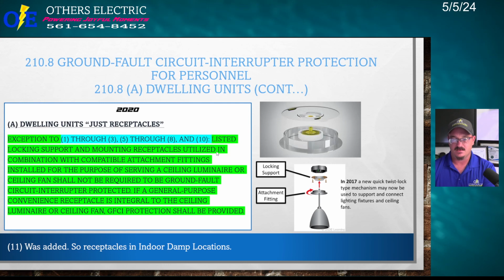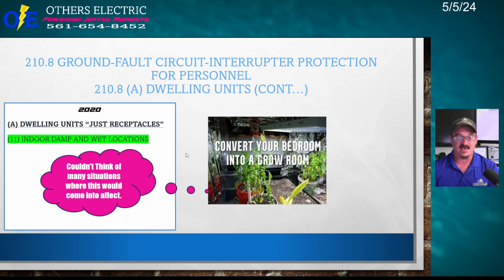All right, let's go back to here. And let's change in here. Okay, they added this, the 11, all right? 210.8A11 is indoor damp and wet locations. So they added this whole 11 to the thing. I couldn't think of many situations where this would come into effect, right? Because what indoor damp locations could you have in a dwelling unit that isn't already included? I'm thinking maybe a steam room, but maybe the grow rooms, right? If you convert your bedroom into a grow room, hey, guess what? That's considered a damp location, and all the receptacles in that grow room have to be GFCI protected, okay? So just know that they added 210.8A11, and it's indoor damp and wet locations.